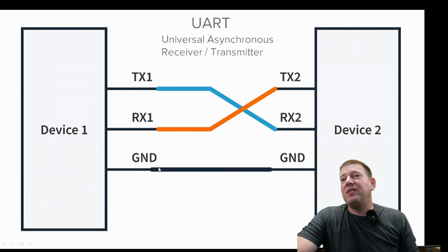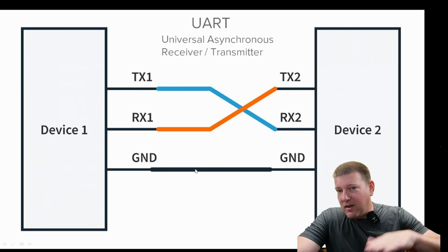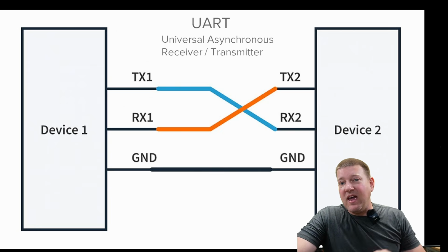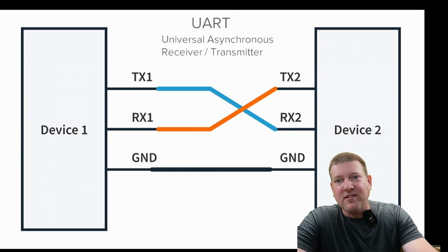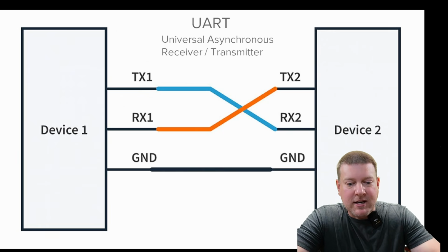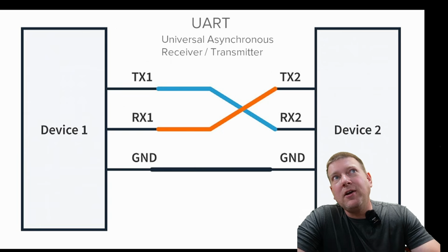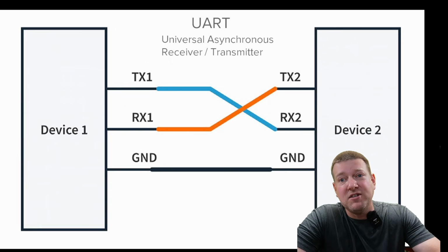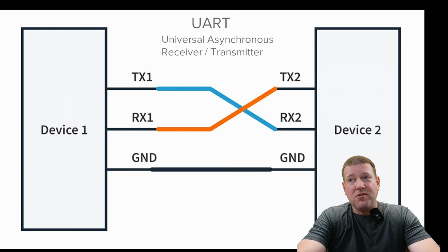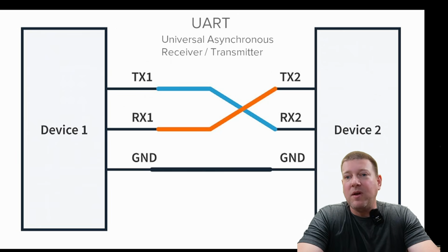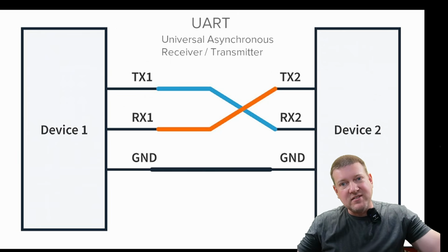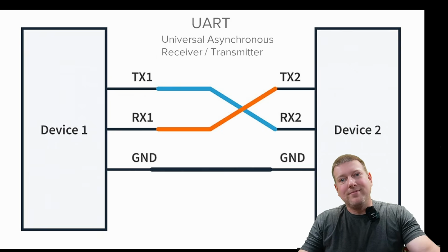And plus, the ground usually keeps the signal noise down, because any long conductor, actually any conductor, it doesn't have to be that long, right? Size doesn't matter, right, ladies? Any conductor out there can and will be an antenna, and it will conduct electricity and noise, and the ground is usually a shielded cable, and that will help keep the noise down, because it dissipates the noise to ground.